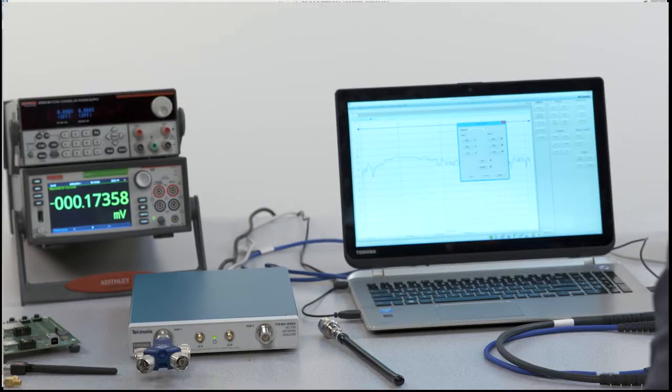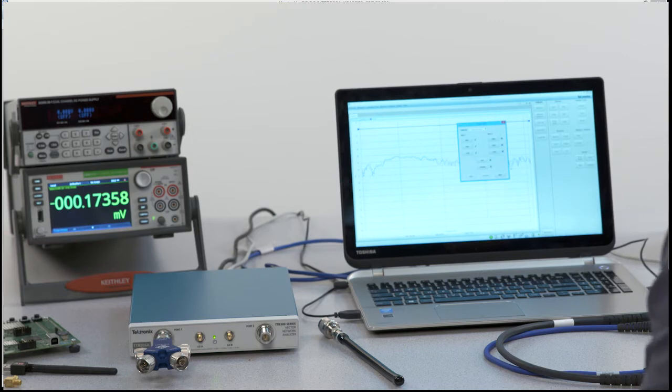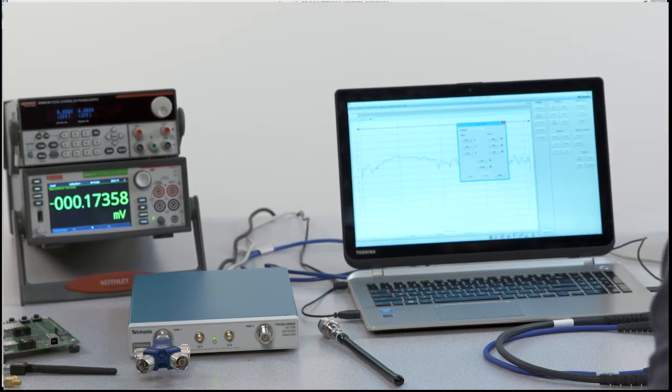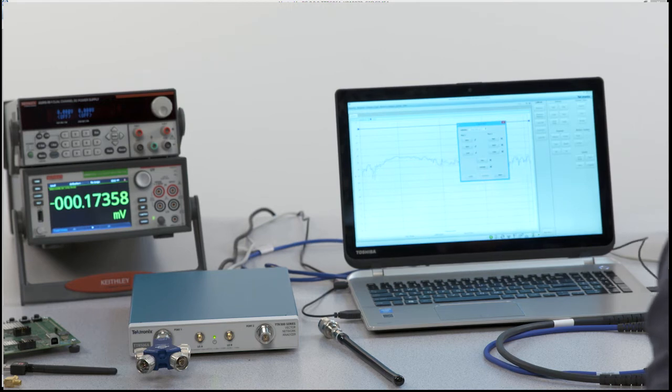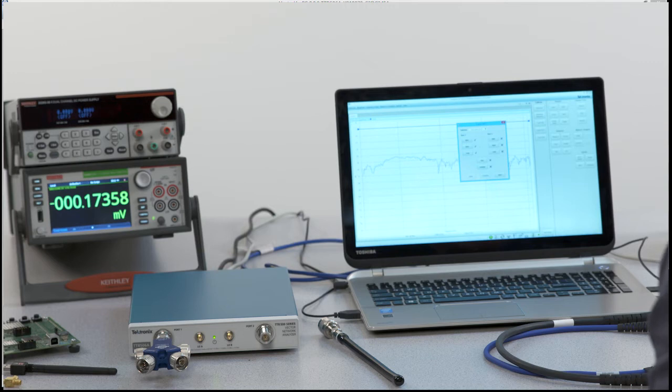Now for all intents and purposes if you went ahead and did a one port cal this would be a complete calibration. You could click apply and you will be completely caled on port 1.